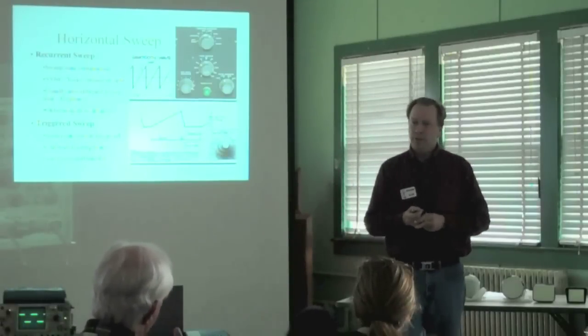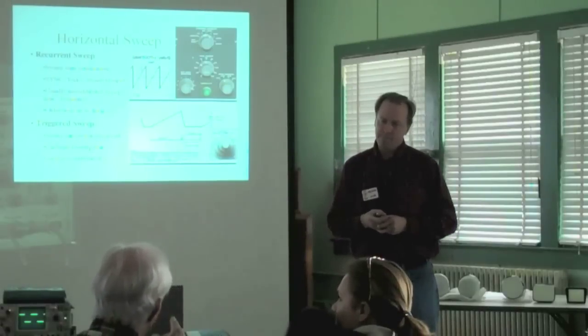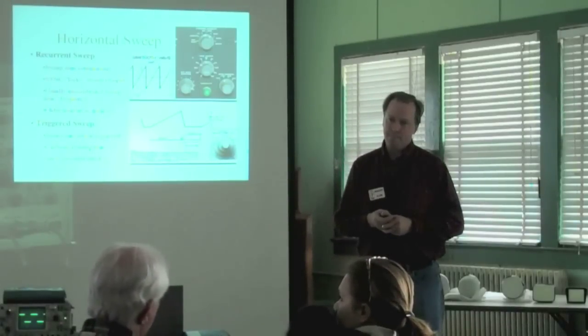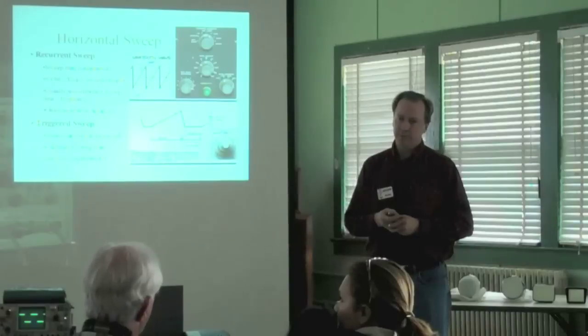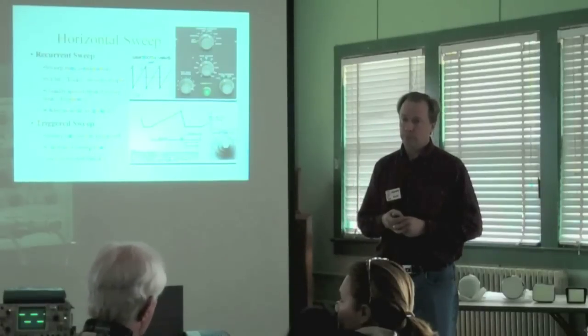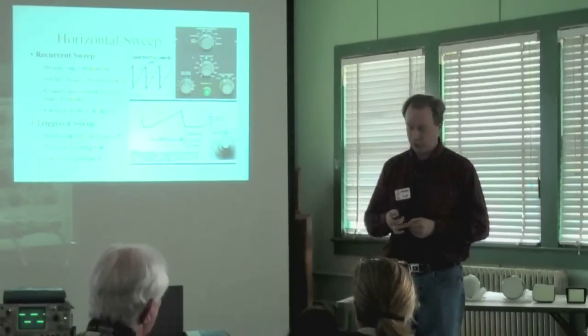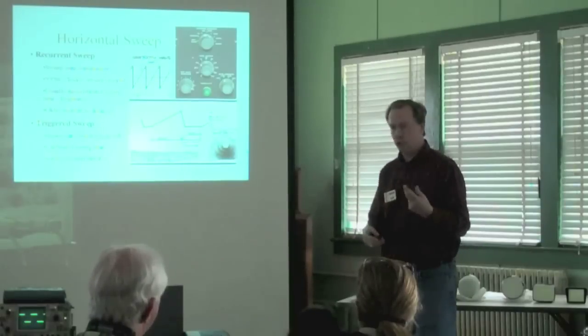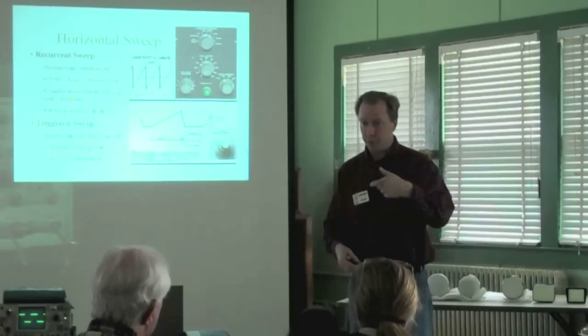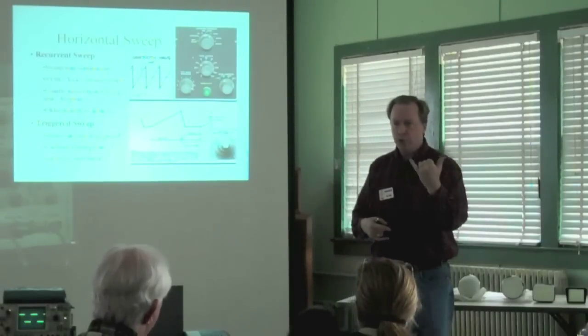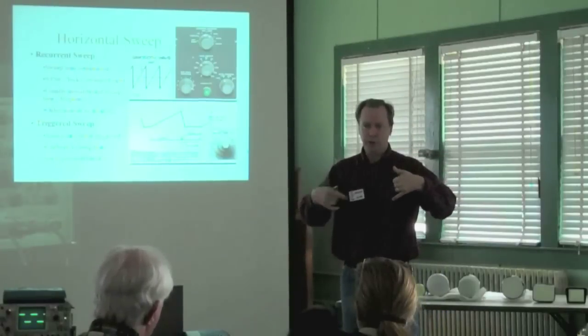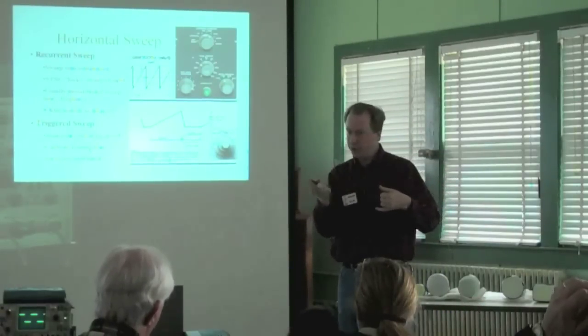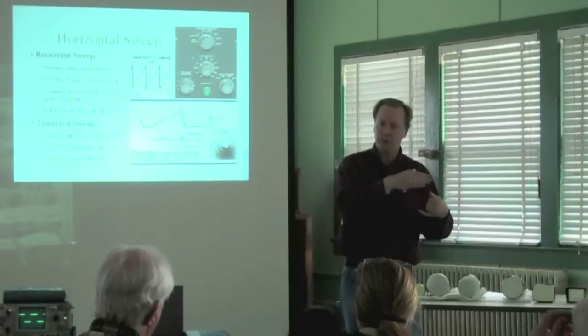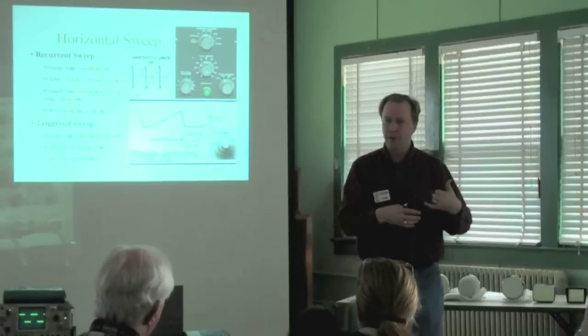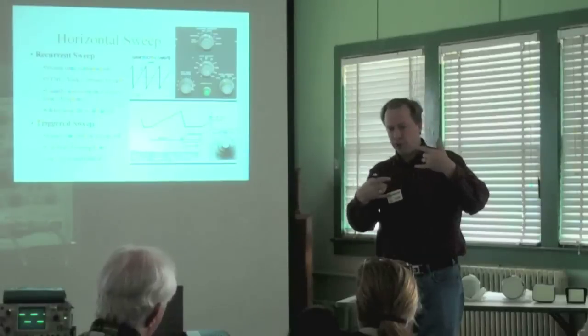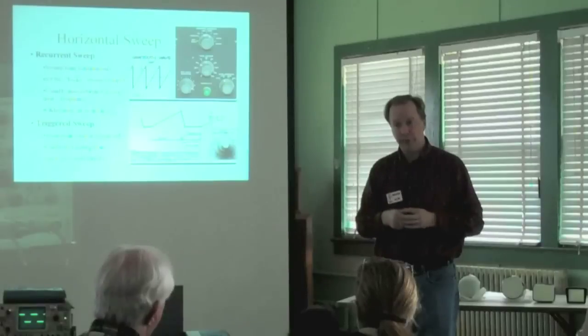The question I was trying to ask is that when you get an older scope, do you have to worry about the possibility of capacitors losing their capability and therefore your timing goes off? Absolutely. Typically the timing will be controlled by R's and C's, but not in a simple RC circuit. The R's would be used to adjust the current that's going to be applied to a fixed capacitor. There might be different capacitors that get switched in. There might be different resistance values that get switched in that control that current. It very well could be that some of those might have changed value and changed the calibration. So absolutely, it will.